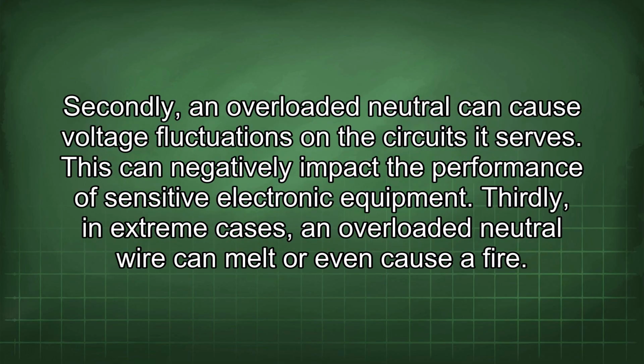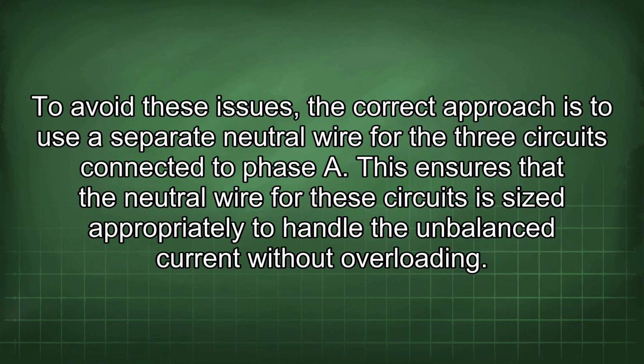Secondly, an overloaded neutral can cause voltage fluctuations on the circuits it serves. This can negatively impact the performance of sensitive electronic equipment. Thirdly, in extreme cases, an overloaded neutral wire can melt or even cause a fire. To avoid these issues, the correct approach is to use a separate neutral wire for the 3 circuits connected to phase A.